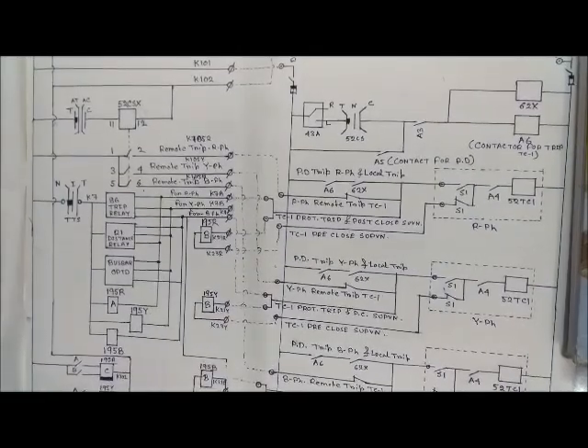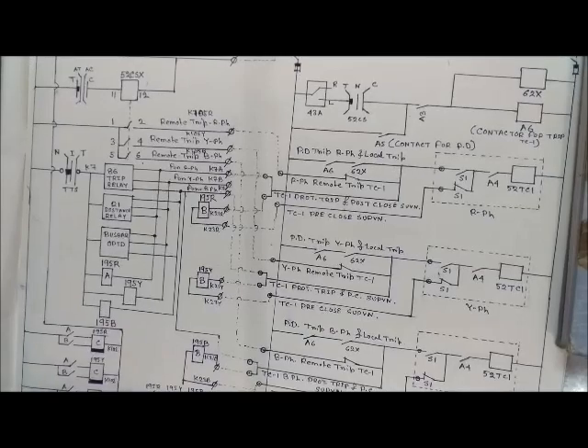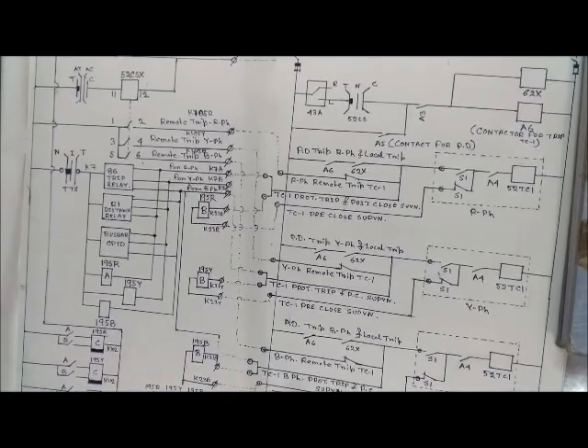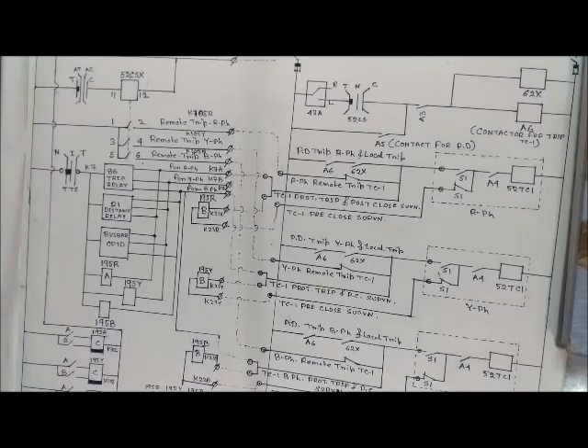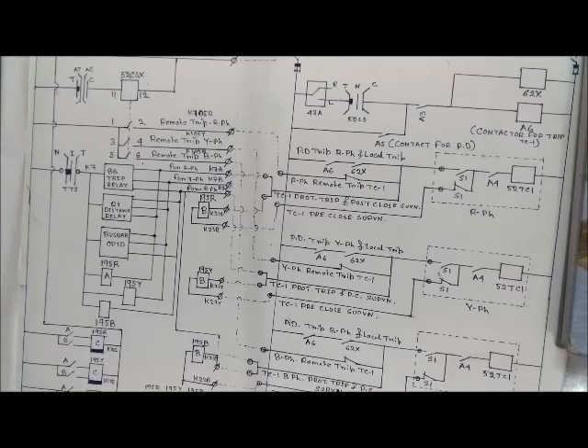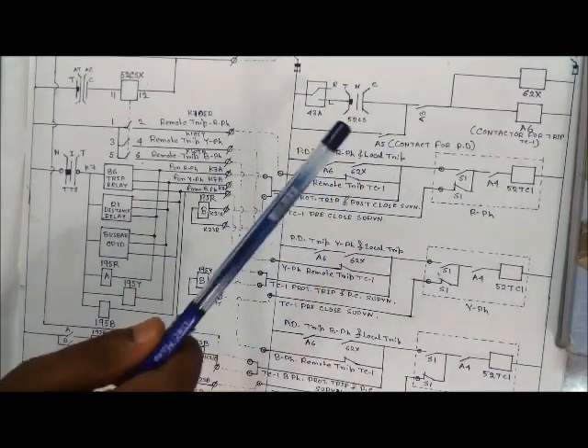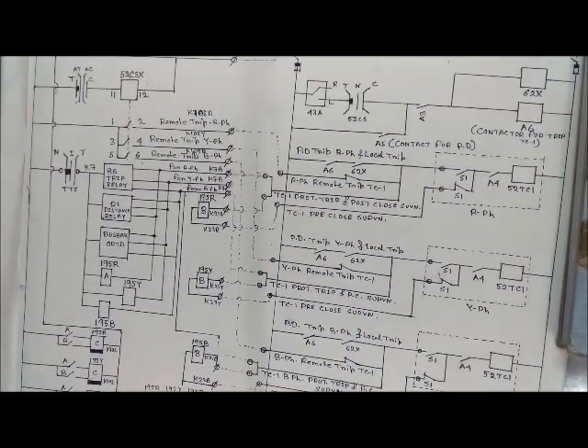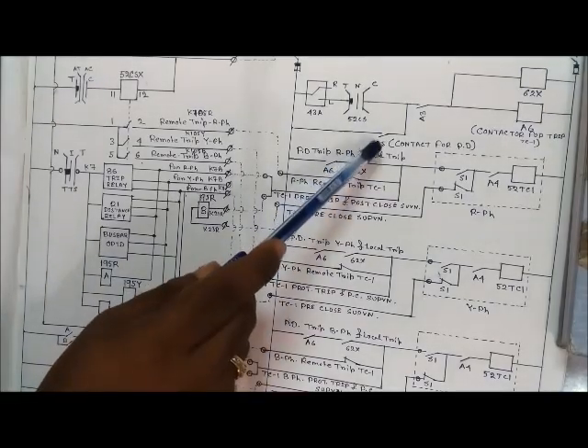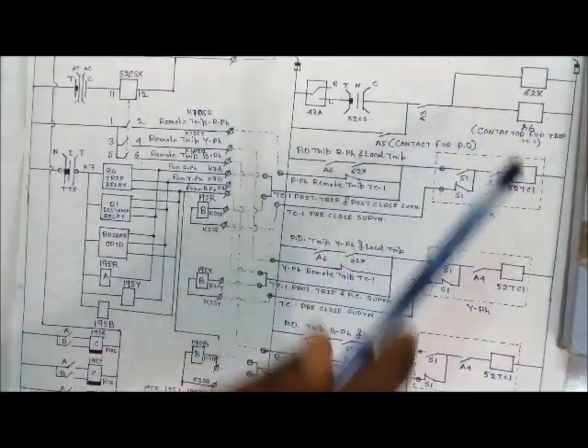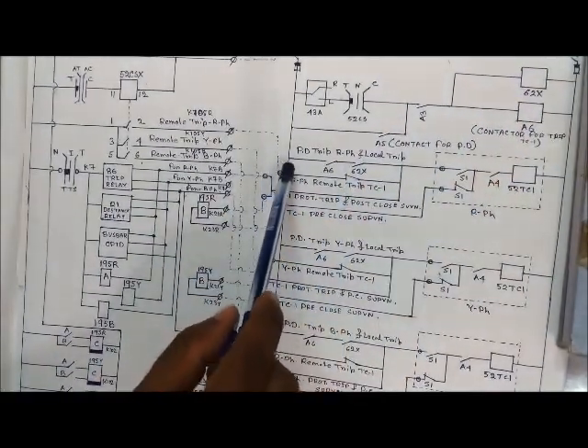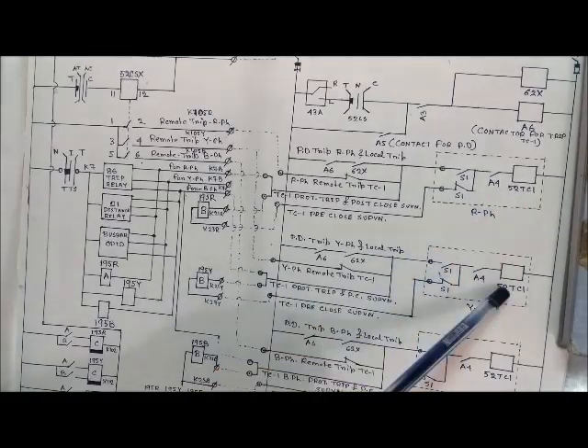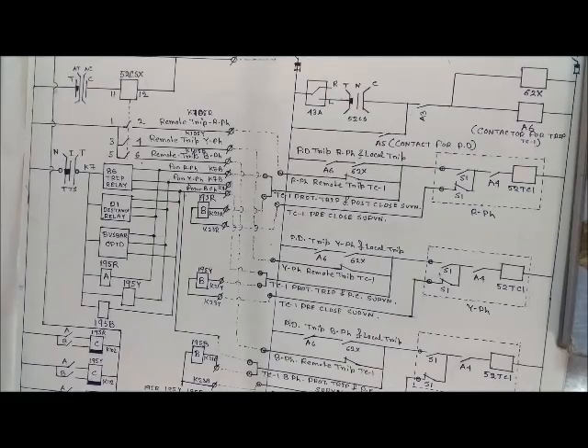For pole discrepancy trip of the circuit breaker, there should be a mismatch of poles — either one or two poles should be in a different ON or OFF condition, i.e., the three poles should not all be in the same position. The A5 relay will energize, and after a time delay of 1.2 to 1.5 seconds, its contact will close. As soon as that contact makes, this relay energizes and gives the tripping pulse to R phase, Y phase, and B phase — tripping all poles of the circuit breaker.